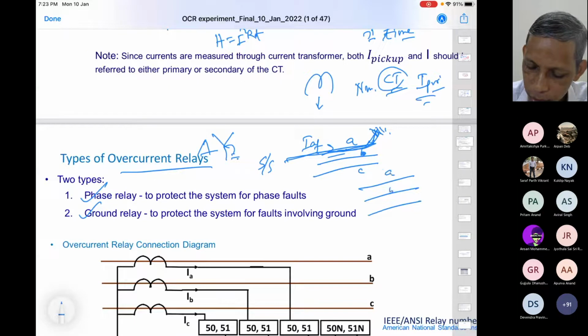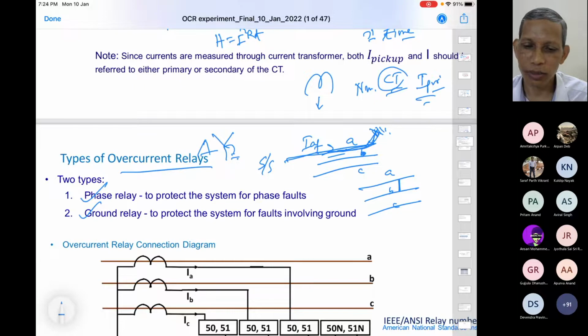This is A, this is B, this is C. Suppose there is a short circuit between these. Someone puts a chain across all three during maintenance, so that even if someone at the substation switches on, the voltage on the right-hand side will be 0. So if you are working in this area, put a chain like this. Agree? Even if someone at the substation side switches on, it will not be detrimental to this side. But many times the maintenance people forget to remove this, and whenever the supply is switched on, it becomes a dead three-phase short circuit. I am telling you about that kind of situation.